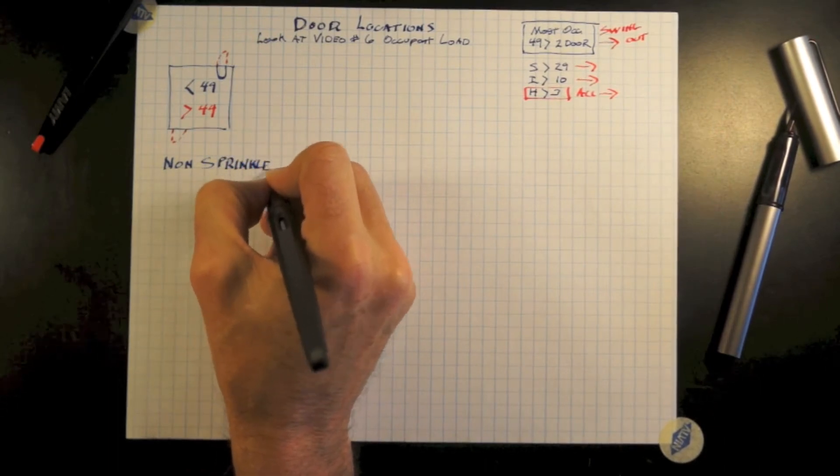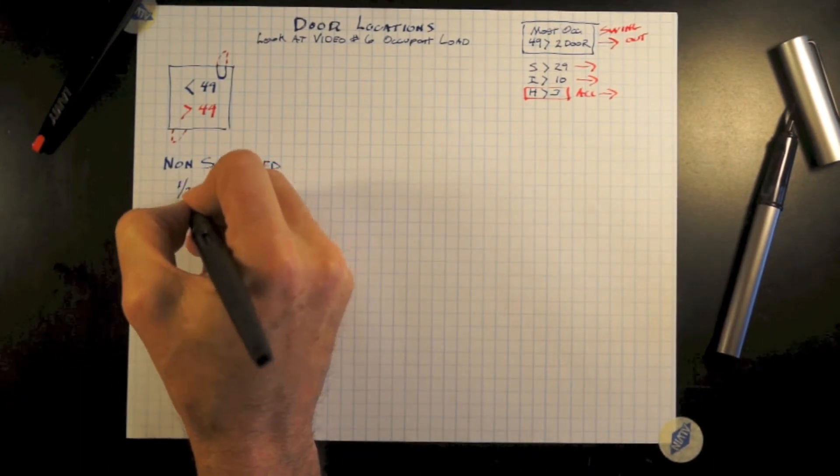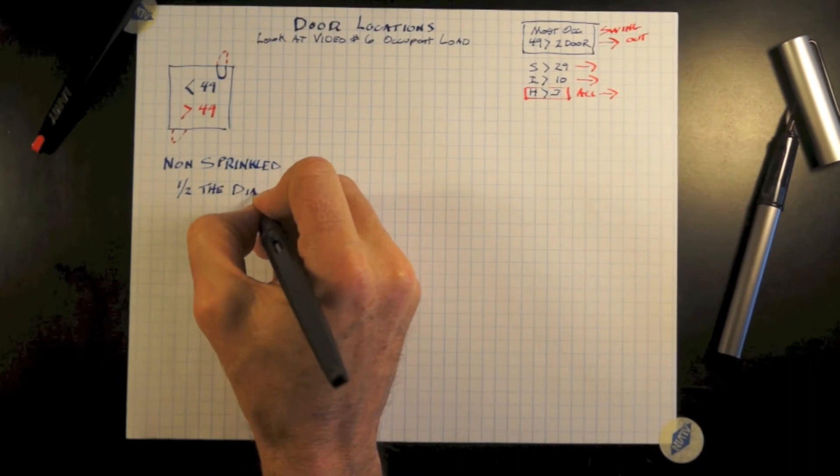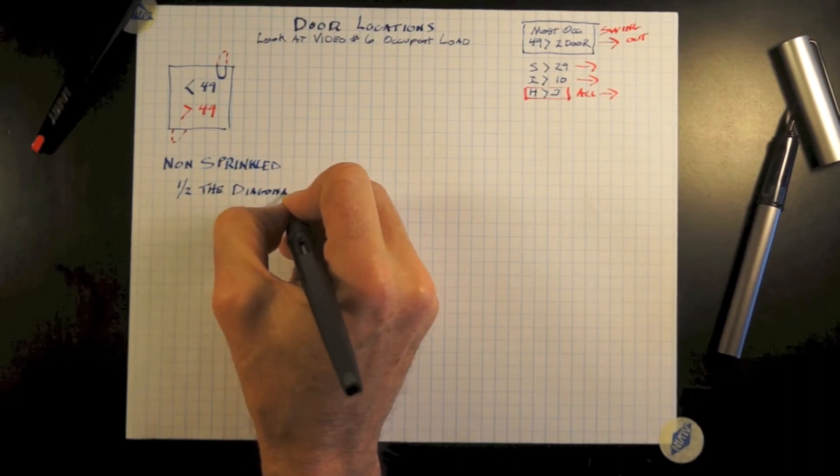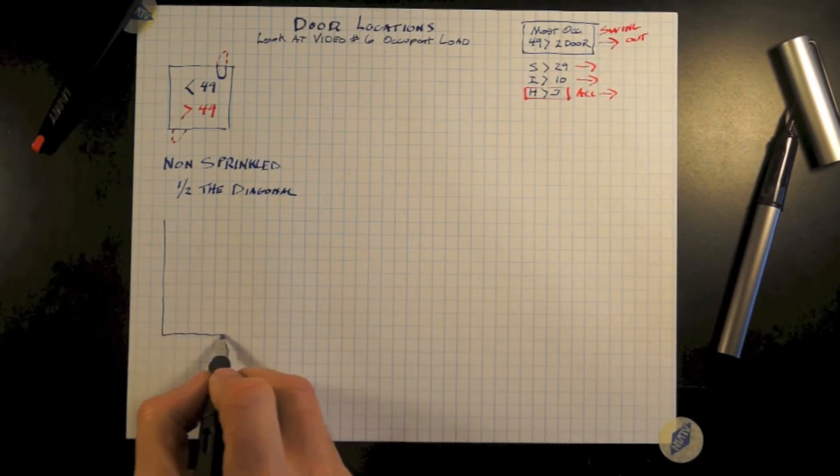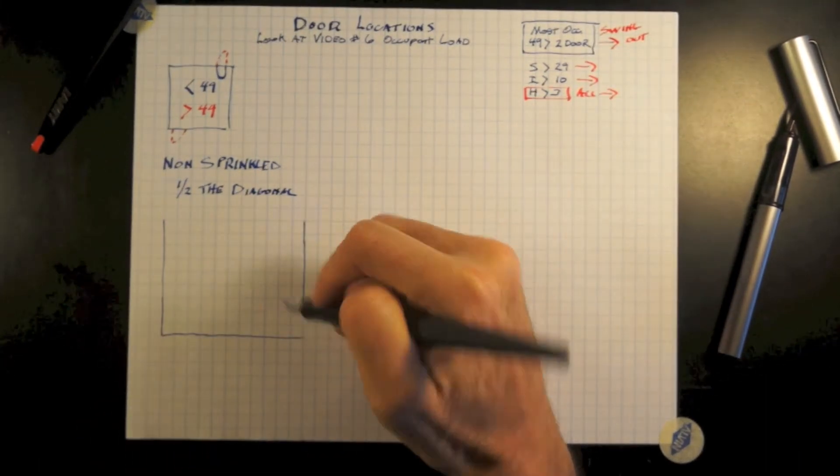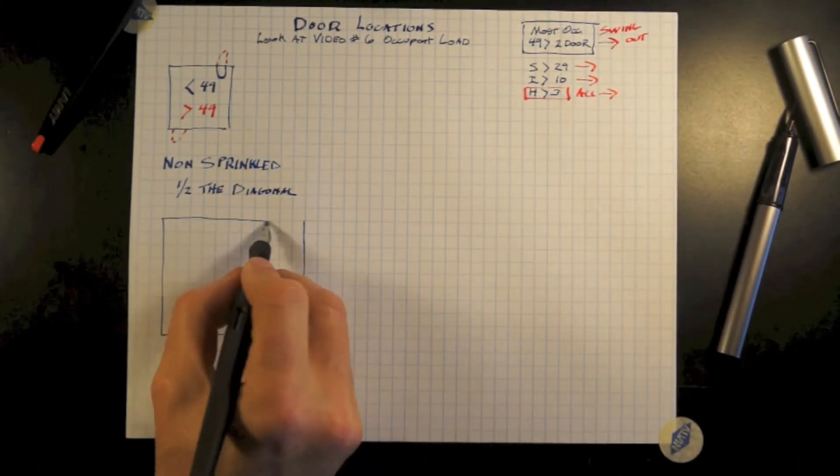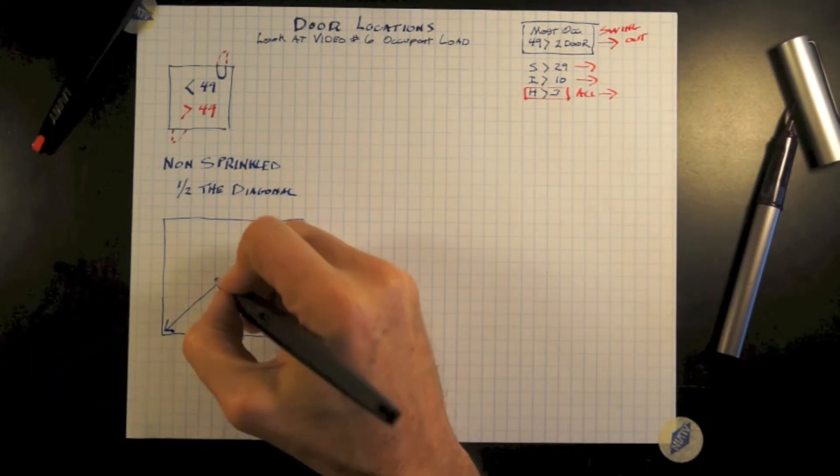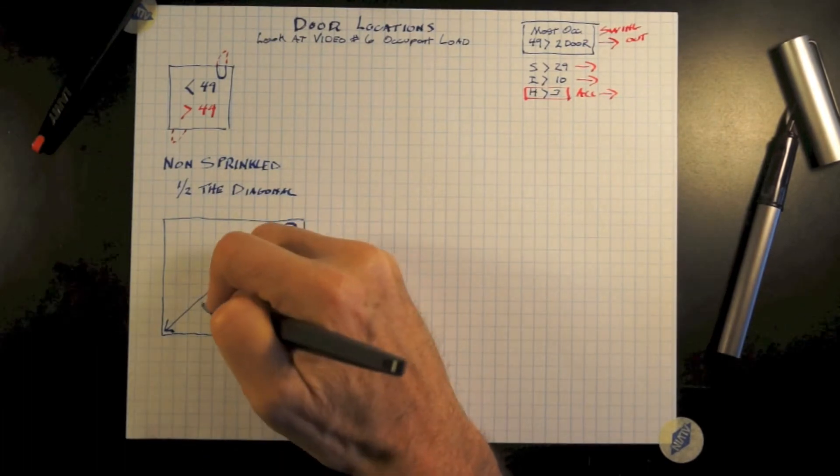Let's start off with non-sprinkled buildings and or non-sprinkled locations. Once we trip needing two doors, those doors shall be located not less than one half the diagonal distance apart or one half the overall longest length of the room apart.